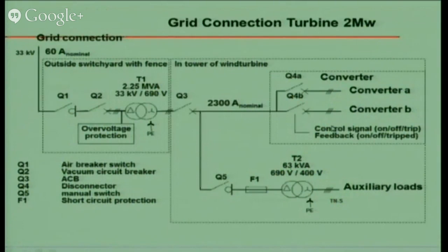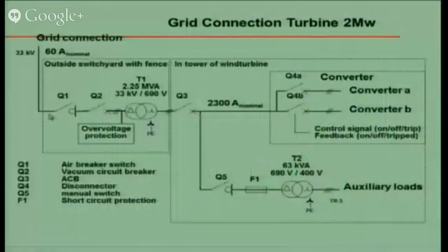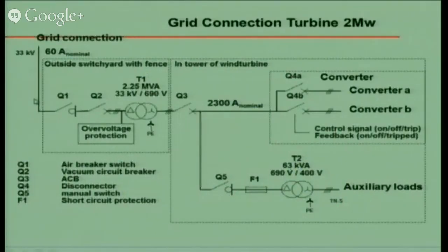To look at how the turbine is connected, here's a picture. This is the turbine, and it is connected to the grid by a 33 kV line. Generally a 33 kV line comes up to the turbine, with a switch, and there has to be a transformer because the turbine generates at different voltages - some at 440, some at 690. So there has to be a transformer matching the capacity of the wind turbine, say 2.25 MVA for a 2 megawatt machine. A transformer is provided there, and then power is transferred to the grid connection.